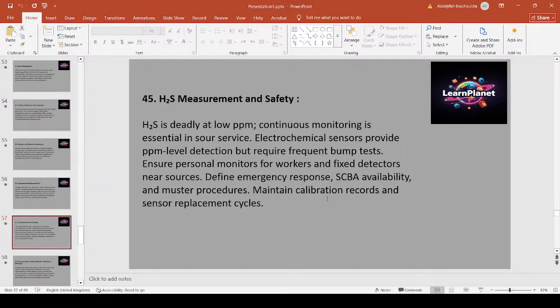H2S measurement and safety. H2S is deadly at low ppm. Continuous monitoring is essential in sour service. Electrochemical sensors provide ppm level detection but require frequent bump tests. Ensure personal monitors for workers and fixed detectors near sources. Define emergency response, SCBA availability, and muster procedures. Maintain calibration records and sensor replacement cycles.